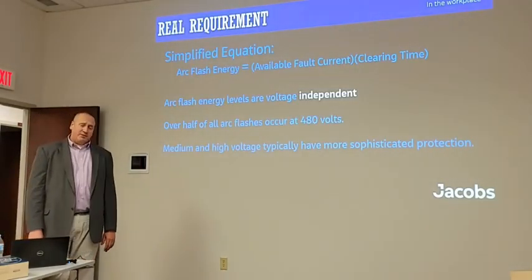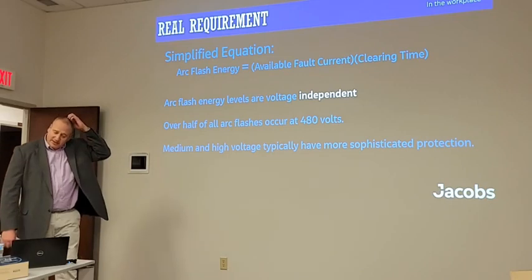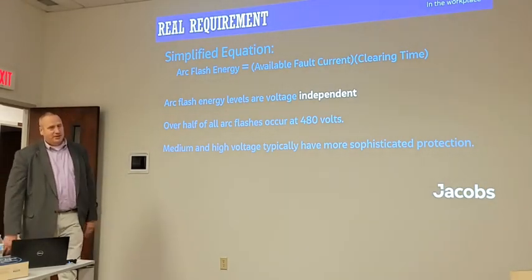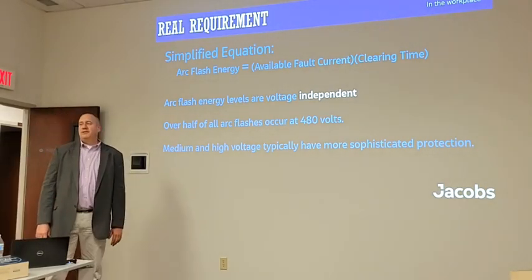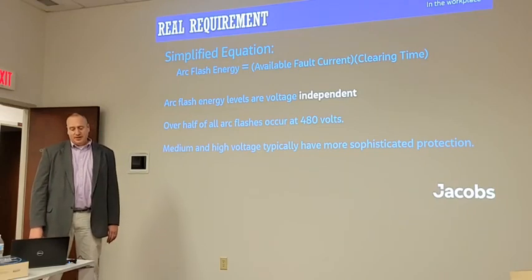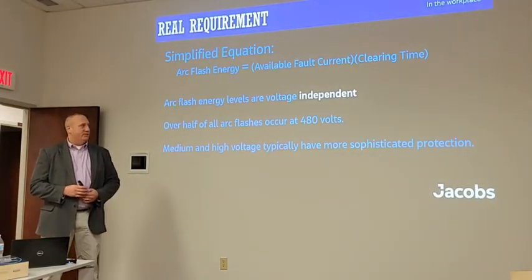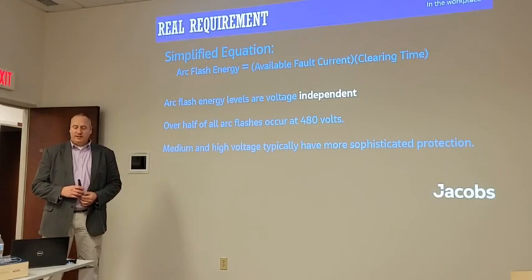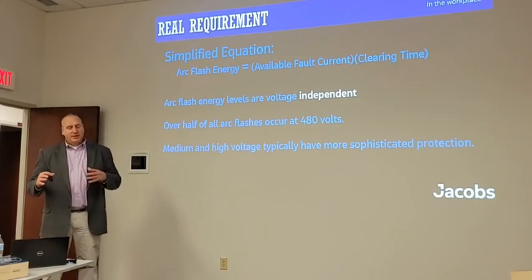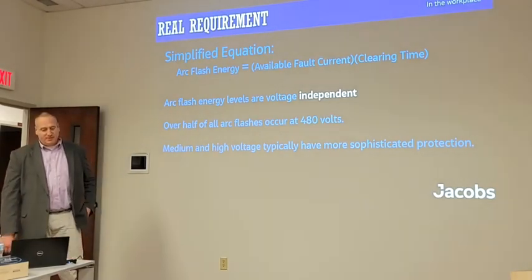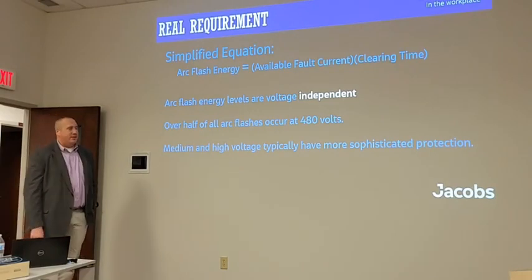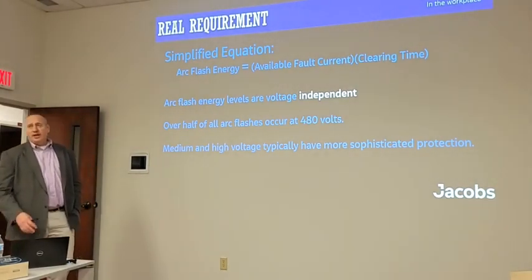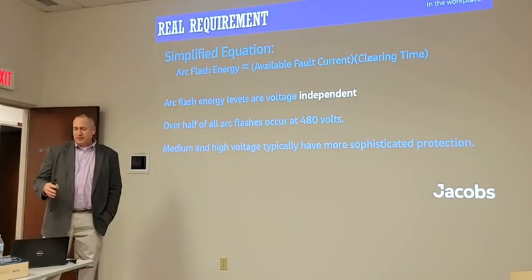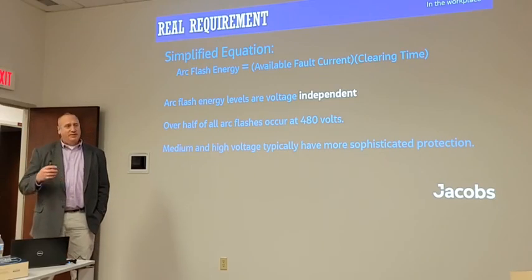Well, there's a simplified equation when it comes to arc flash, and that's essentially your available fault current times the amount of time it takes to clear that fault. The arc flash energy levels are voltage independent. It has more to do with the fault current and the clearing time. In fact, over half of all arc flashes occur at 480 volts. And out of all the analysis and evaluations that I've seen, the vast majority of the really high energy levels are at 480 volts.